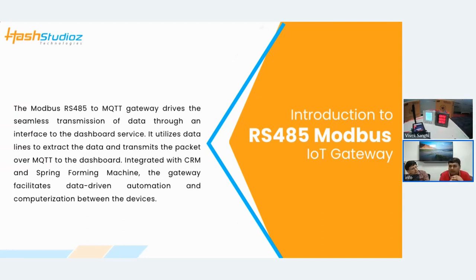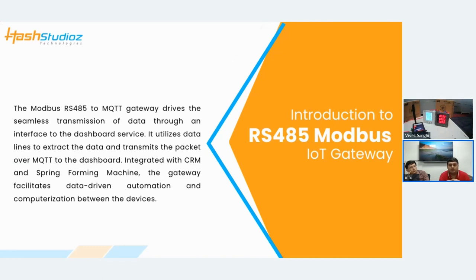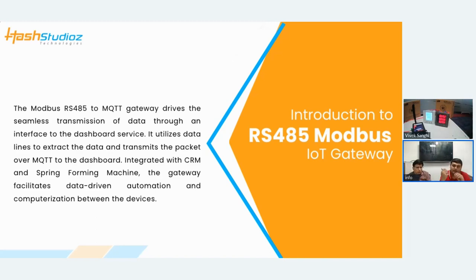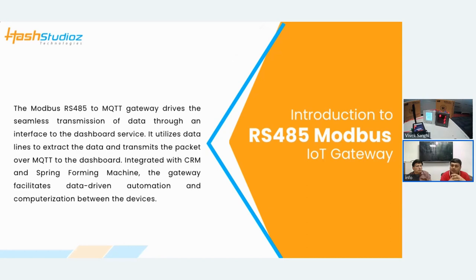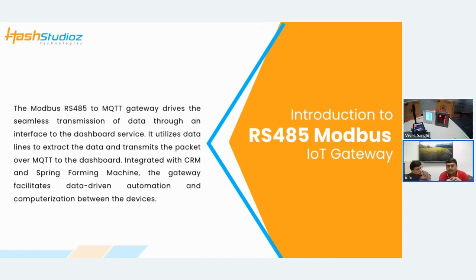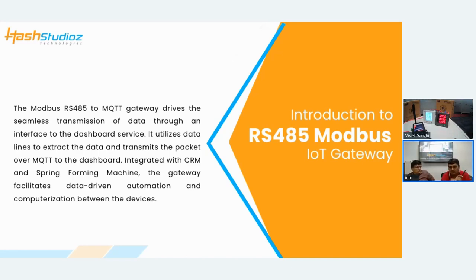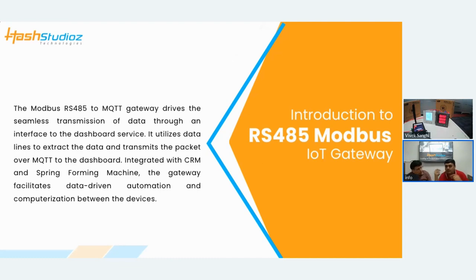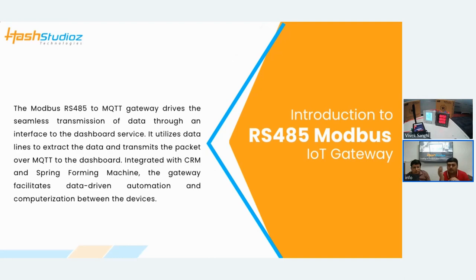MQTT is the transmission protocol. But when we talk about data, we are mostly talking about either the data is being collected or generated or transmitted through RS-485 or RS-232. RS-232 is your specific serial protocol and RS-485 is your industrial modbus protocol in which a two-line pair is used to transmit data for about 1.2 kilometers on the same channel, connecting up to 255 slaves that can be polled. The transmission medium is half duplex. The half duplex meaning that one device in the network speaks and it waits for the respective device to respond back. The communication happens in serialized form so that each slave is being polled again and again for their data.